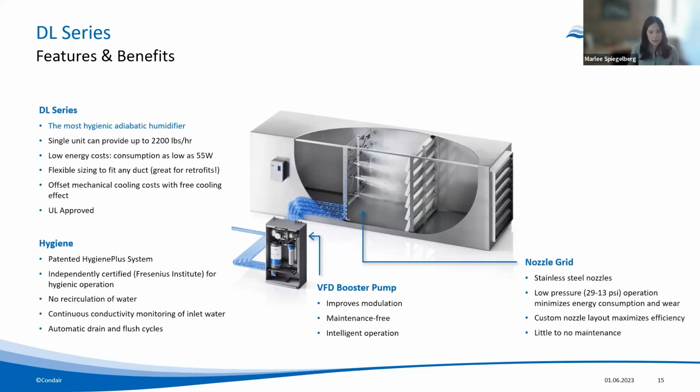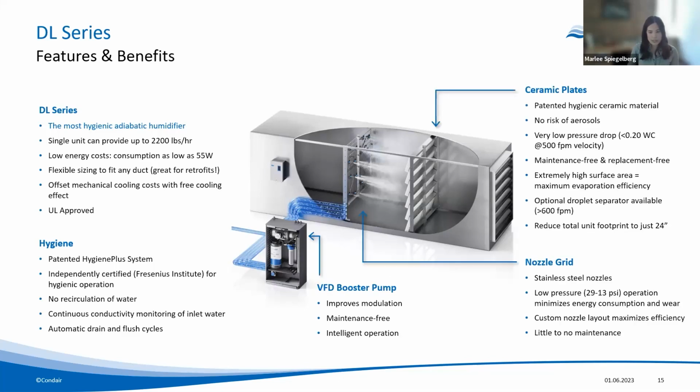And then finally, our ceramic plates. This is a patented design and is a Condair exclusive. It significantly reduces the water waste by evaporating water not absorbed by that nozzle section, creating a water efficiency over 90%. The ceramics also remain dry, meaning very hygienic operation.